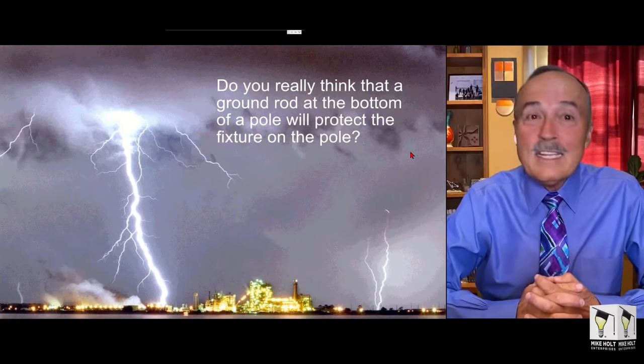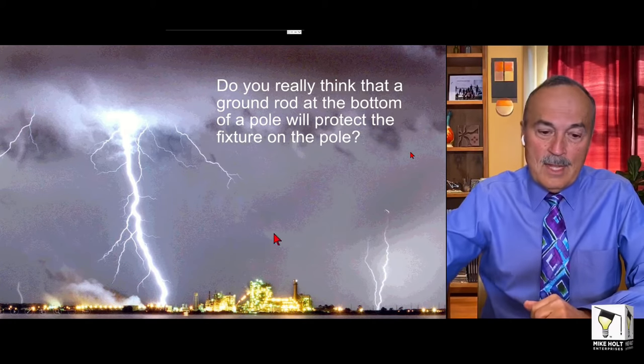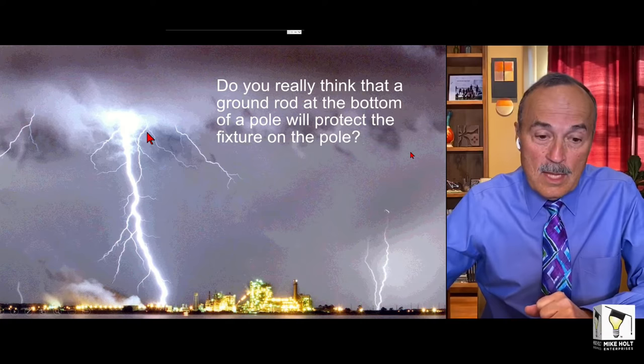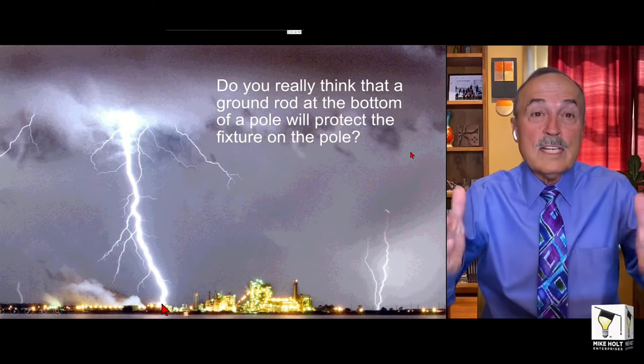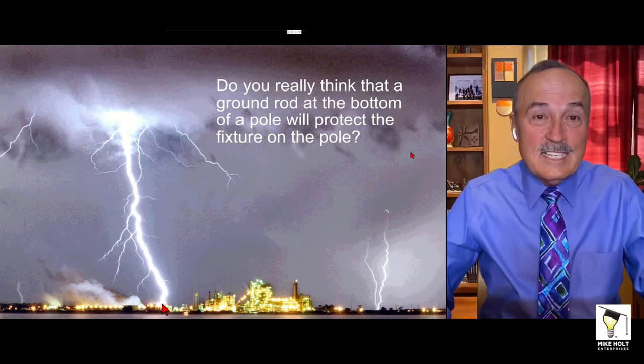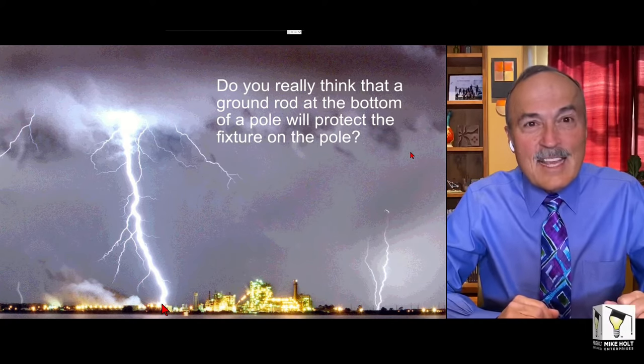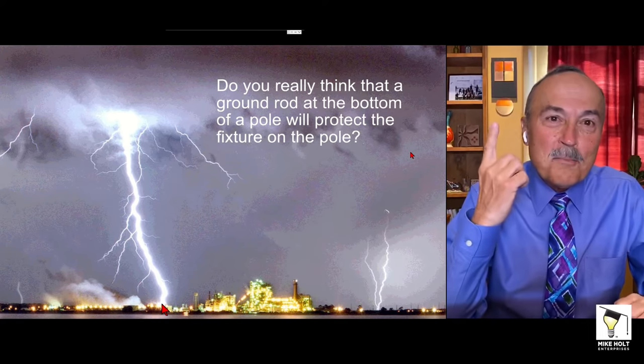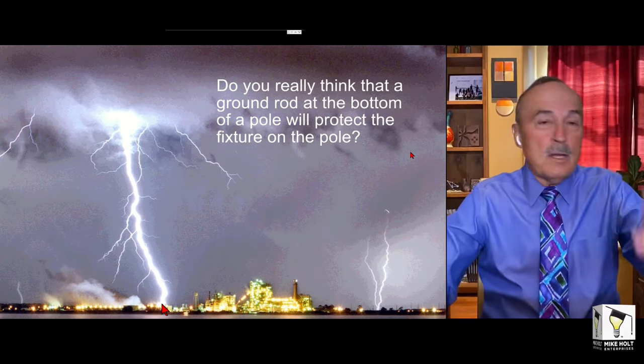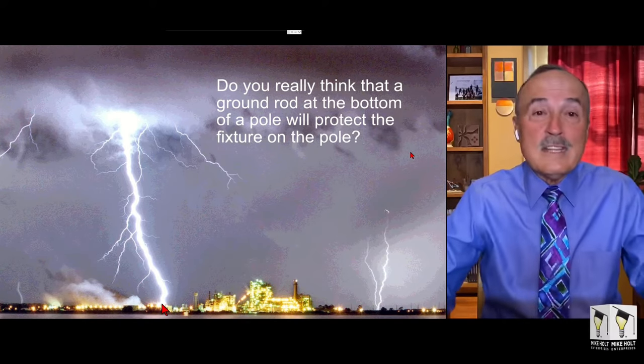Back to the question: does the ground rod at a pole serve something? Imagine a light pole with a light fixture on top. A lightning bolt comes down - you saw what it does to a tree, cuts it in half. Do you really think a ground rod at the bottom of a pole is going to protect that little LED fixture on top? People were driving ground rods because they thought that's what made it safe from electricity because it was 'grounded.' Grounding doesn't make anything safe.